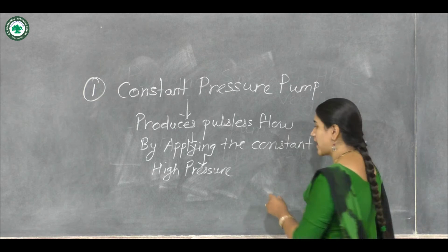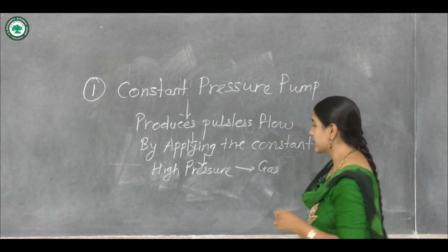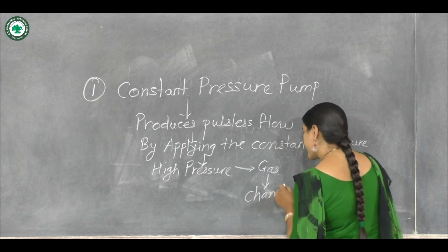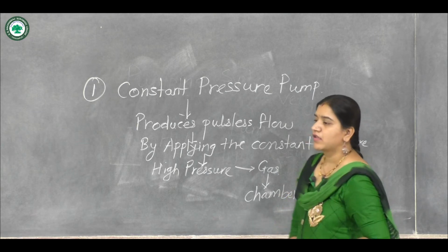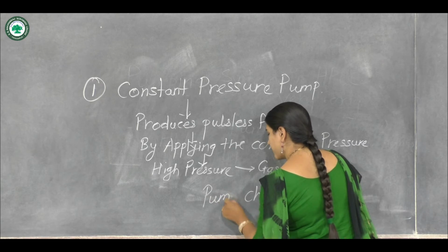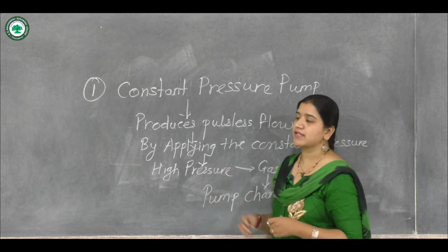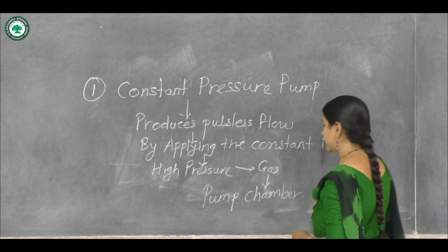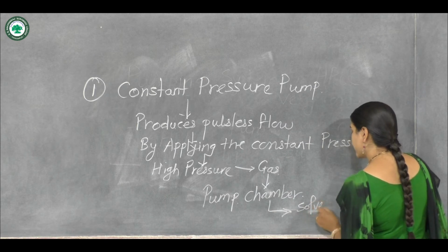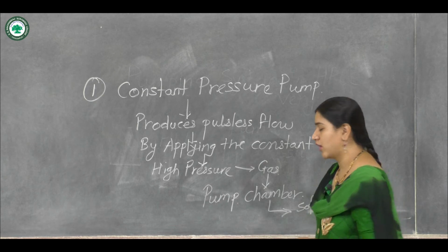This high pressure is applied over the gas and it forces the gas to pass inside the pump chamber, which helps the normal flow of a solvent through the column.